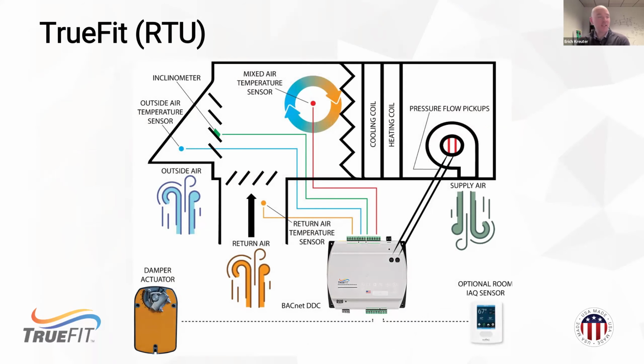To give you a little lay of the land, we've got an equipment schematic of a typical installation on a rooftop, or small pieces of packaged equipment. So we'll see that the core of the system is that TrueFit AFMS controller there in gray. This is built on the backbone of our BACnet devices, so it's all native BACnet out of the box. And there's a few different sensors that are connected to it that give us all of these airflow measurement metrics.